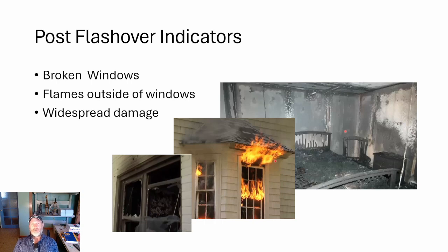His conclusion was based upon the fact that there were no remnants of glass at the base of the window, so it had blasted a considerable distance away. Likewise, there was a parking gate that was knocked over, shown in these photographs. So he concluded, and was about ready to testify in court, that this was most likely an explosion-related event. We came to find out, after talking more with the owners, that the fire department knocked down that road barricade when they came in, and the owners explained that this is a summer camp, not a heated nor a permanently occupied facility. Consequently, there was no glass in those windows.